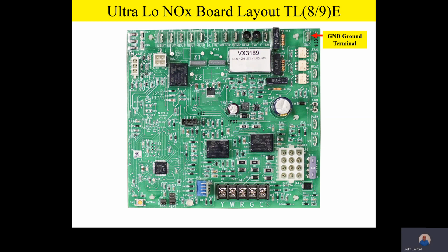As we move down the right-hand side of the board, we see there's a 24 volt fan terminal. Now, team, this 24 volt fan terminal is an isolated terminal that allows continuous fan operation if the homeowner or the building owner goes to the thermostat sub-base assembly and switches the fan from auto to on.